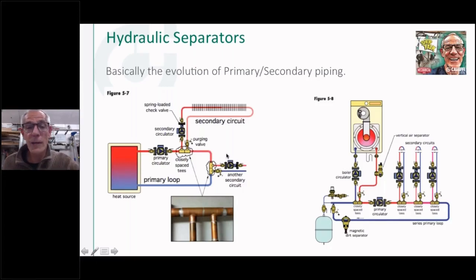So if you walk into a job and somebody tells you, oh yeah, I piped it out primary secondary, and you look around the room and you don't see two T's close together within a couple inches of one another, with a pump on one side pumping out of those T's and coming back in the other side, it's not a primary secondary. If this pipe was connected down here on the return, it's no longer primary secondary. So it has to be those T's closely spaced together. It was fairly understandable once you understood what was happening between there.